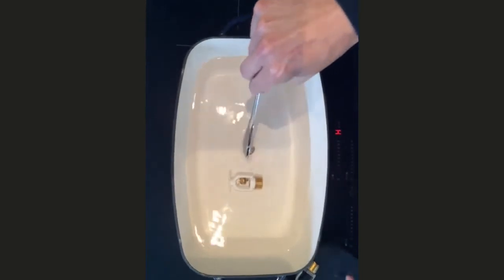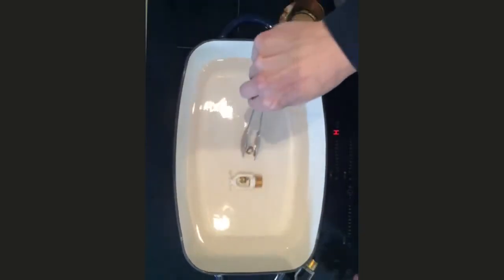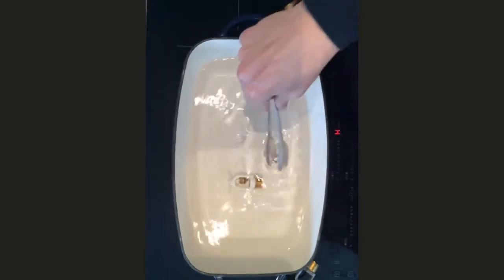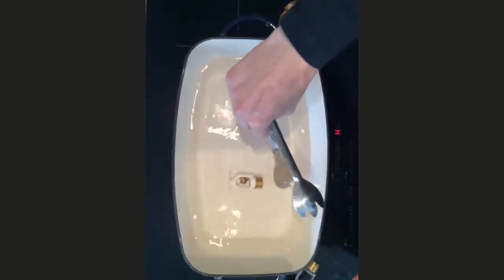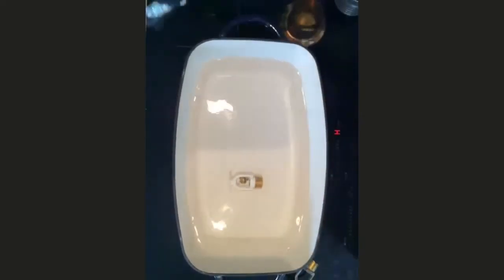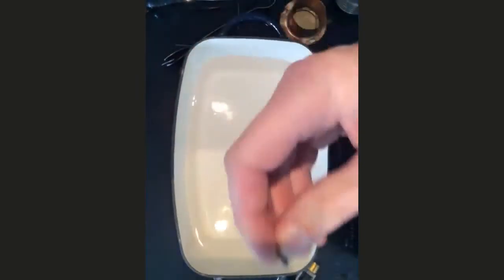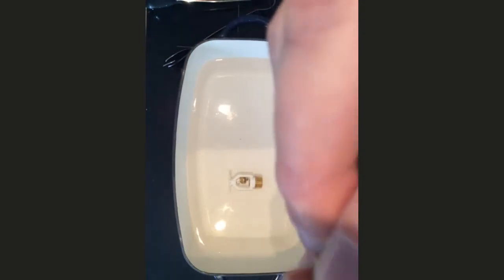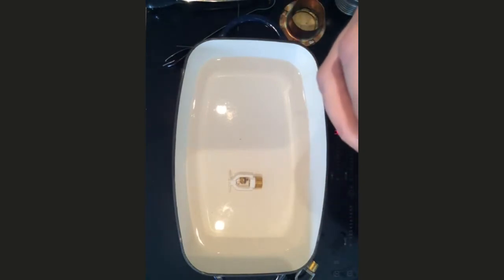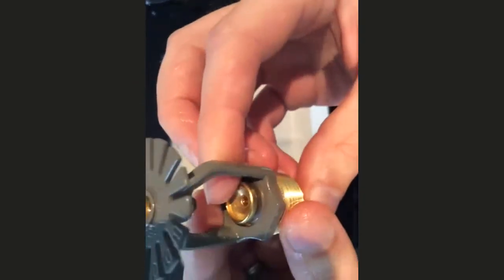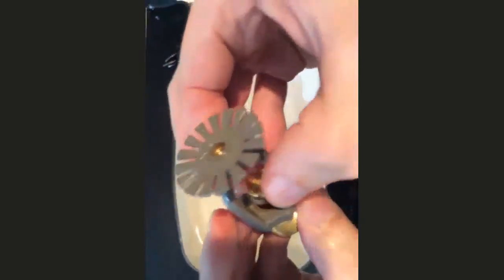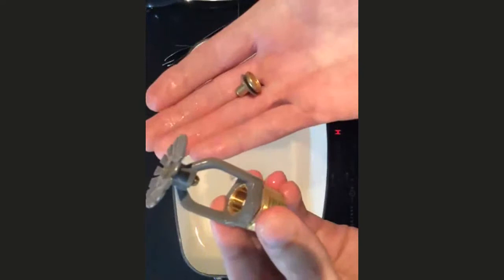The other bits is we've got these two little metal pieces, and obviously some glass as well. Quite tricky to get that out. There. So we've got two other bits to do with the sprinkler head itself. Kind of got this rubberized piece, which is obviously going to help to keep the water from leaking out. So that's how it was in the head, with the bulb obviously in the gap, and then that has come apart to let the water out.